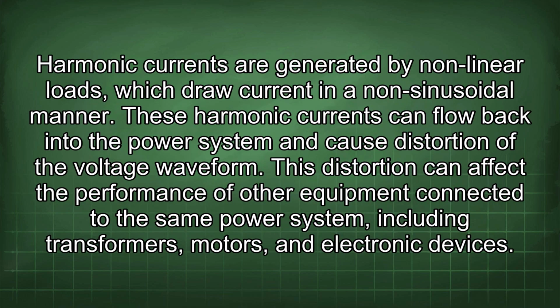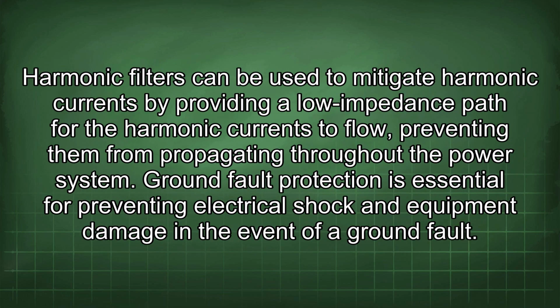Harmonic currents are generated by nonlinear loads, which draw current in a non-sinusoidal manner. These harmonic currents can flow back into the power system and cause distortion of the voltage waveform. This distortion can affect the performance of other equipment connected to the same power system, including transformers, motors, and electronic devices. Harmonic filters can be used to mitigate harmonic currents by providing a low impedance path for the harmonic currents to flow.